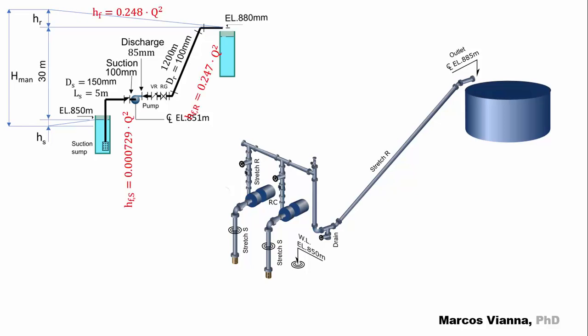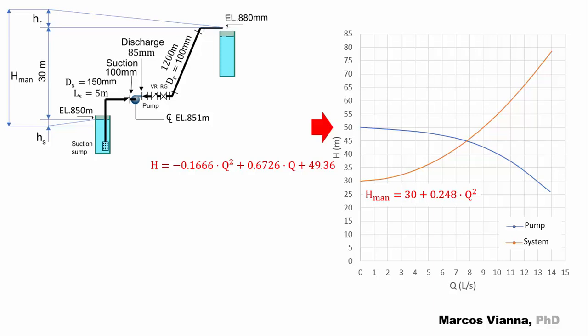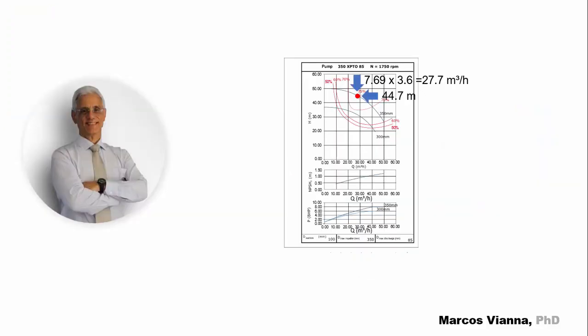Here are the head losses equations that occur in the systems. They were derived in another video of this channel. Its link is in the description. And now, here is the equation of the pump when we consider the 350 mm diameter impeller. When we put these equations together, we find this second degree equation, which allows us to find the coordinates of the operating point. Here is the point in the pump chart. Notice that the flow was converted to cubic meters per hour.